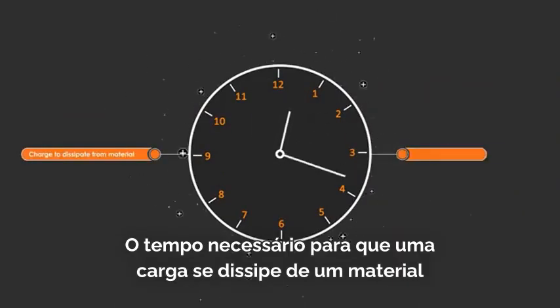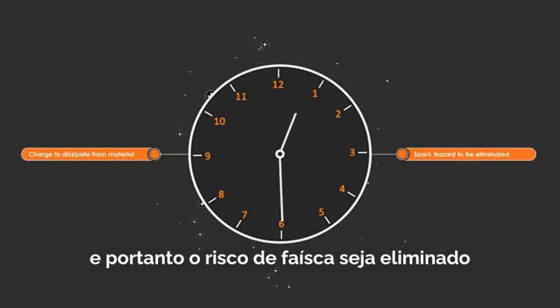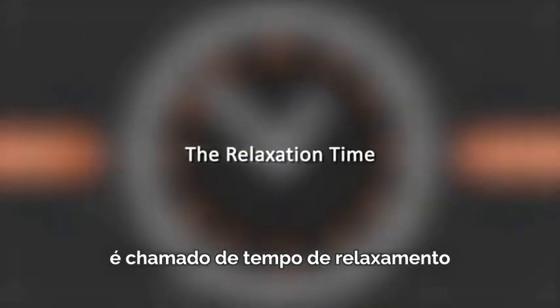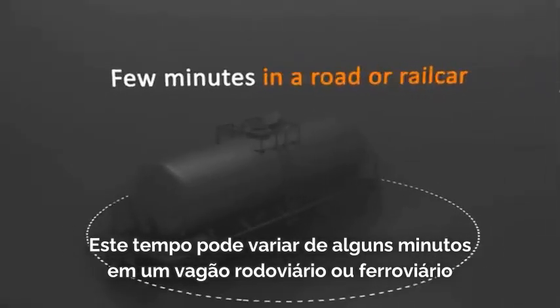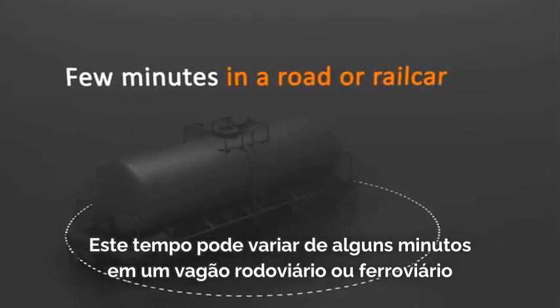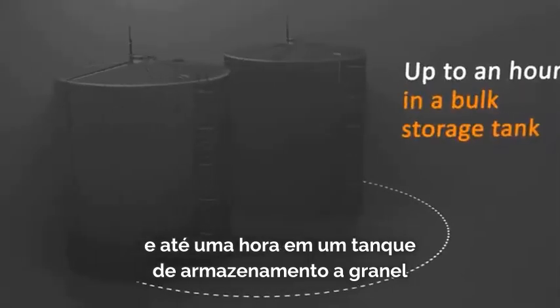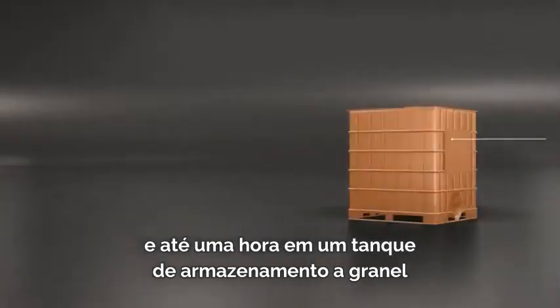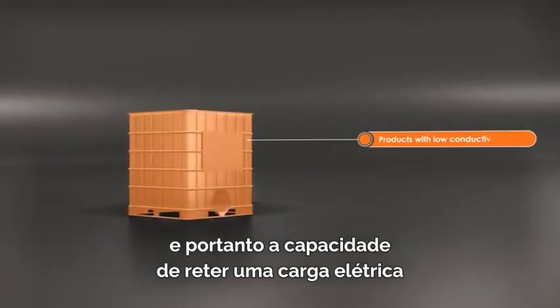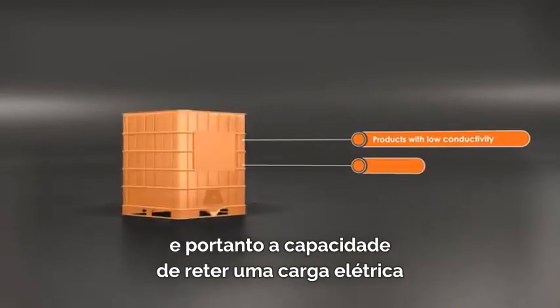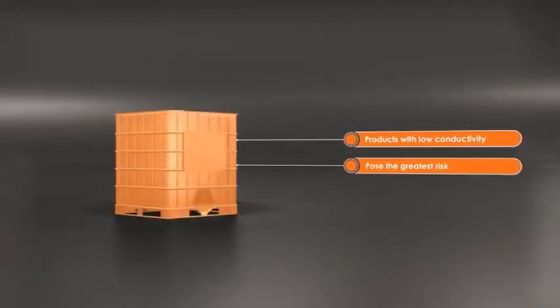The time taken for a charge to dissipate from a material, and hence the spark hazard to be eliminated, is called the relaxation time. This time can range from a few minutes in a road or rail car and up to an hour in a bulk storage tank. Products with low conductivity, and hence the ability to retain an electrical charge, pose the greatest risk.